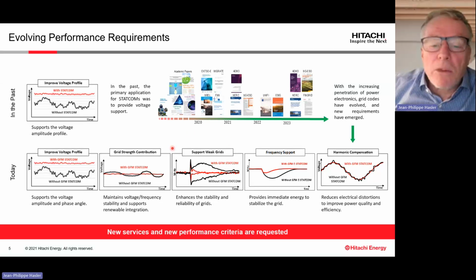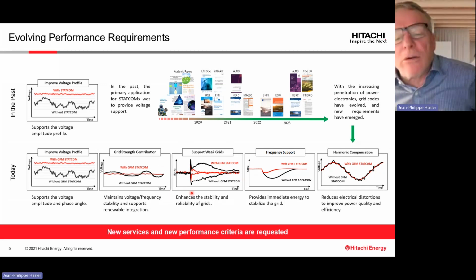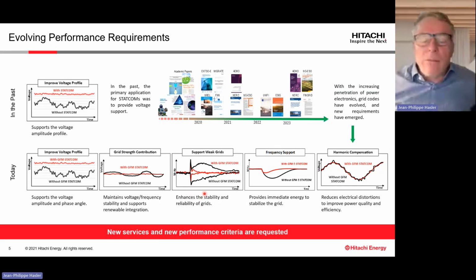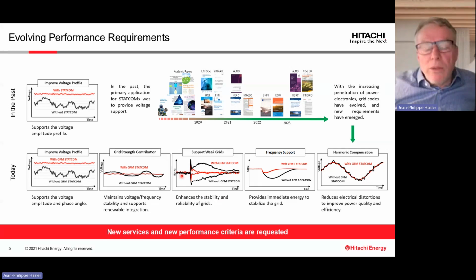We are also talking about the support for weak grid, and that is especially to support some remote device or generation, which may be at a very remote place. And then you also have to ensure that all these converters are able to operate, that means they can inject their power, and that is what we call support for weak grid, which is exactly the same functionality. I have to say we have to increase the grid strength.